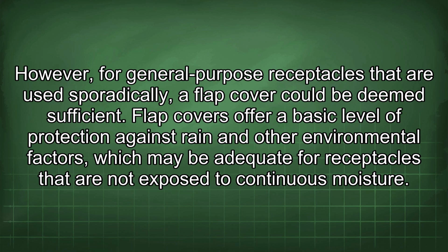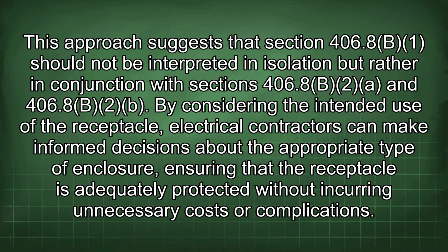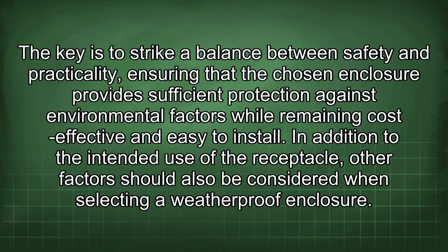Flap covers offer a basic level of protection against rain and other environmental factors, which may be adequate for receptacles that are not exposed to continuous moisture. This approach suggests that Section 406.8(B)(1) should not be interpreted in isolation, but rather in conjunction with Sections 406.8(B)(2)(a) and 406.8(B)(2)(b). By considering the intended use of the receptacle, electrical contractors can make informed decisions about the appropriate type of enclosure, ensuring that the receptacle is adequately protected without incurring unnecessary costs or complications. The key is to strike a balance between safety and practicality, ensuring that the chosen enclosure provides sufficient protection against environmental factors while remaining cost-effective and easy to install.